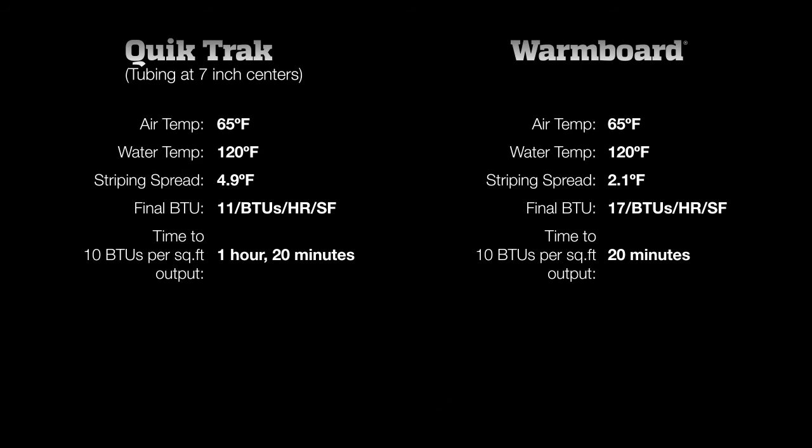At the end of the test, Quik Trak's surface temperatures varied by almost 5 degrees — a difference you can feel as you walk across the floor. WarmBoard, on the other hand, is just above 2 degrees, too subtle to be noticed.